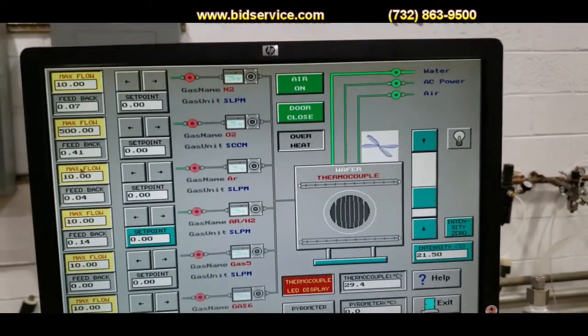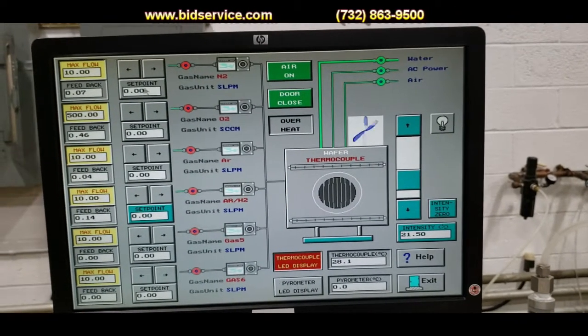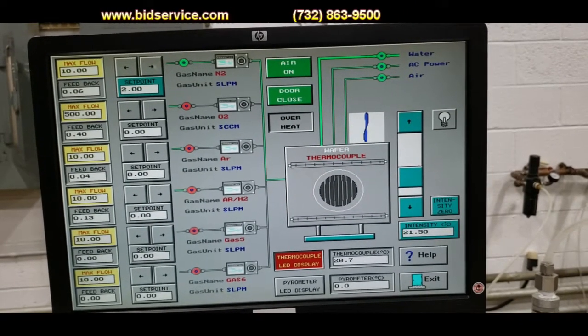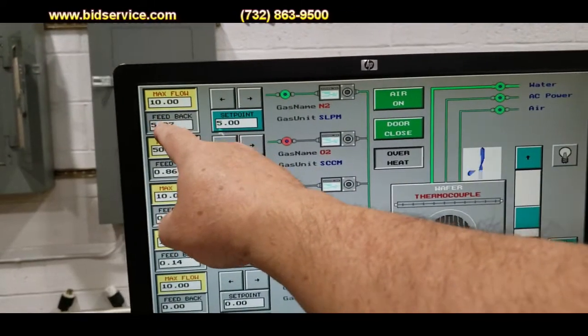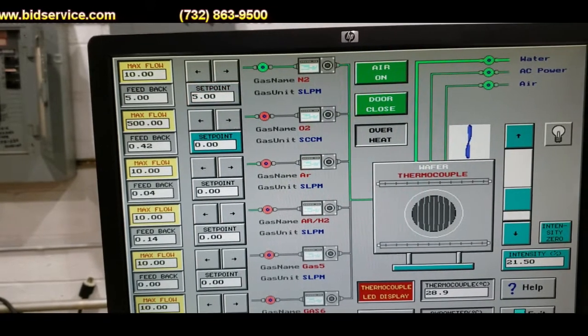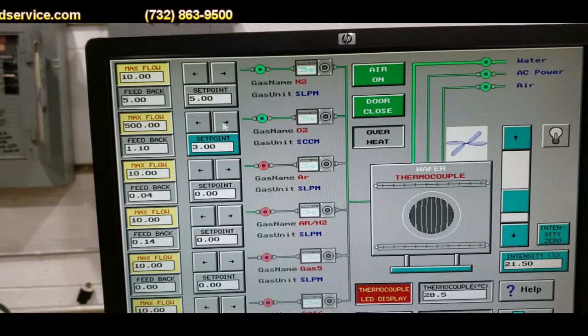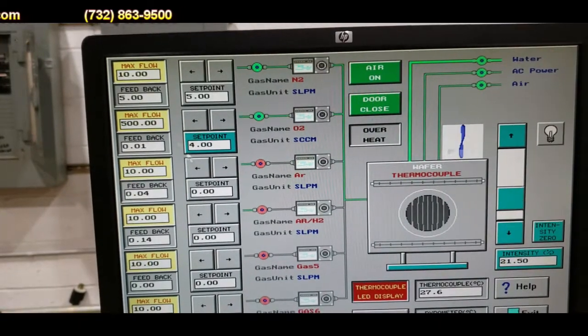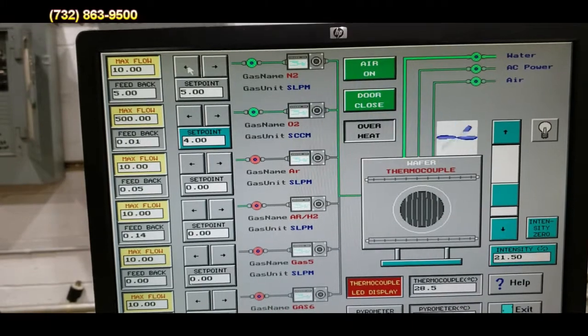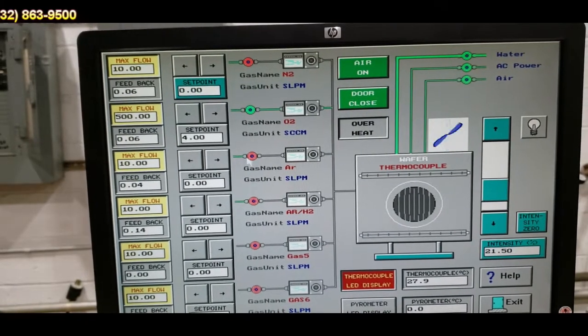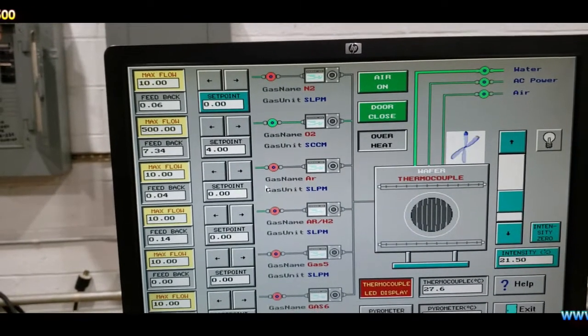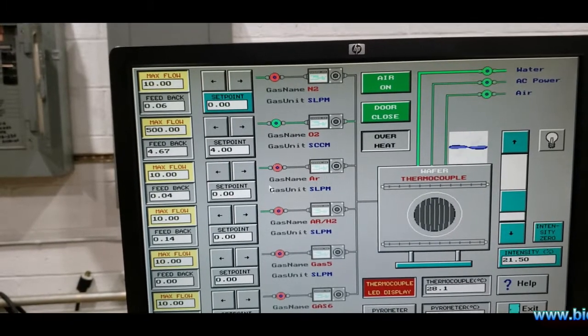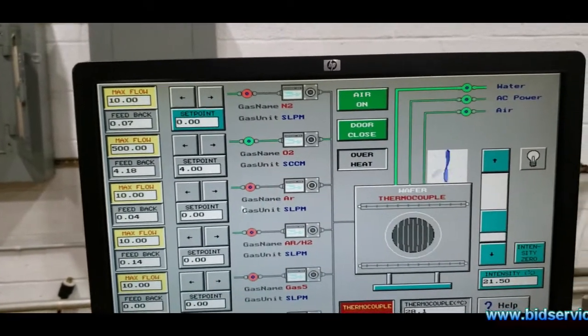The second part of this test we are going to do is check out the MFCs. So I am going right up to the top right here and I am just going to turn this on and start. You can see I got the set point at 5 right now and you can see the feedback right now is at 5. I will go ahead and do the second one. I have it set at 4. And now you can see it is coming into 4 right now.